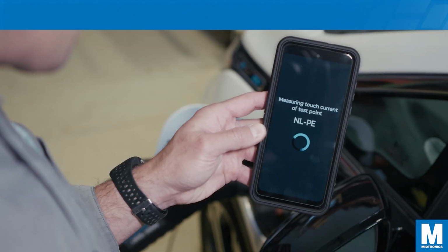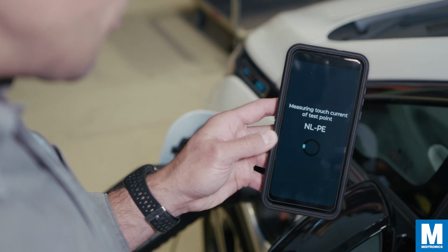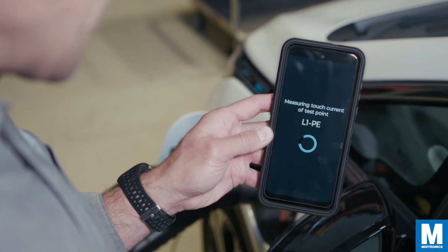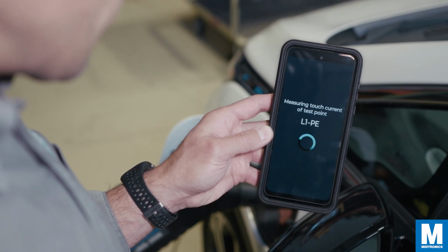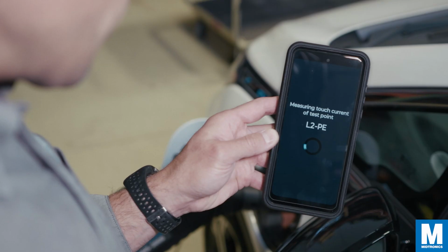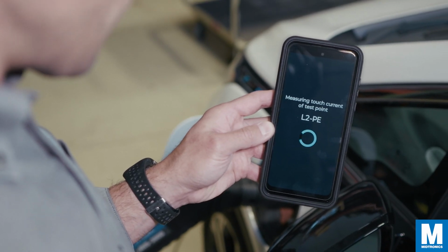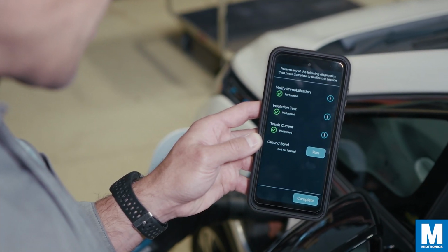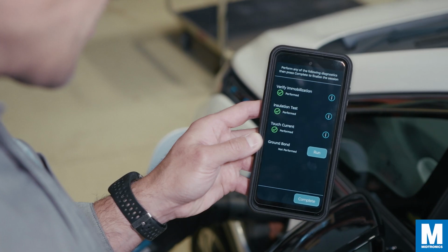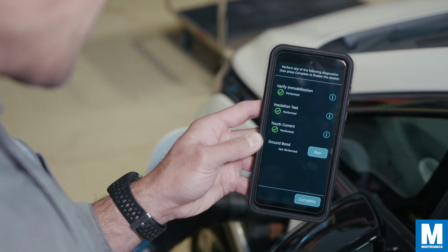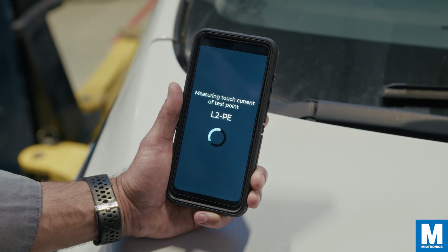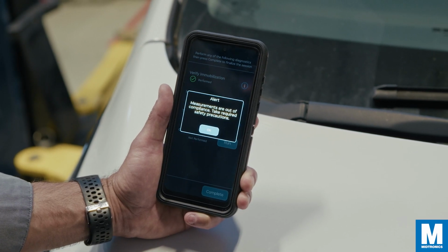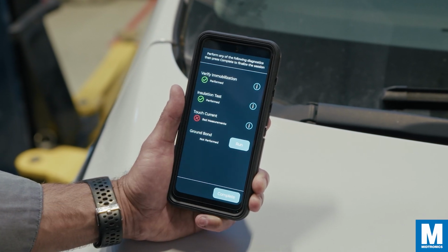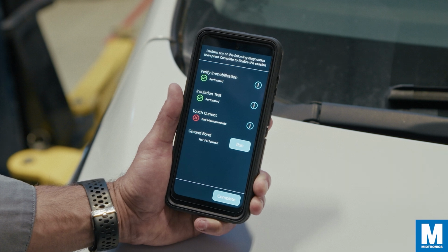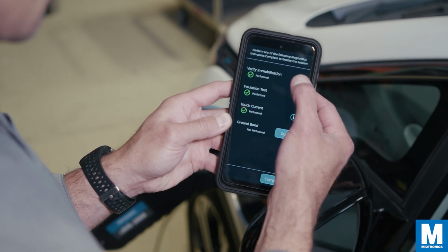If you tap Yes to confirm immobilization, the xHVS will automatically proceed through both the AC insulation and AC touch current tests. Results for both tests will be displayed upon completion. These tests automatically follow the immobilization test. The controller will return to the main test screen, allowing you to initiate the ground bond test. If any measurements from these tests are non-compliant, you will receive an alert. To have a more detailed view of the results, you can tap the eye next to each test.